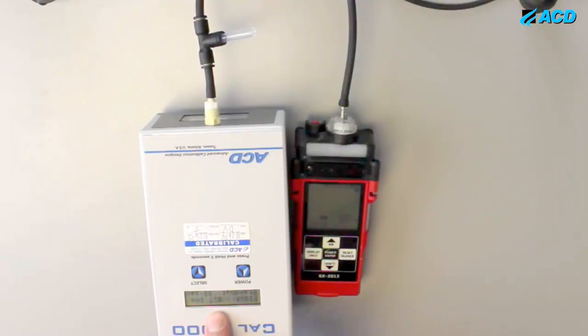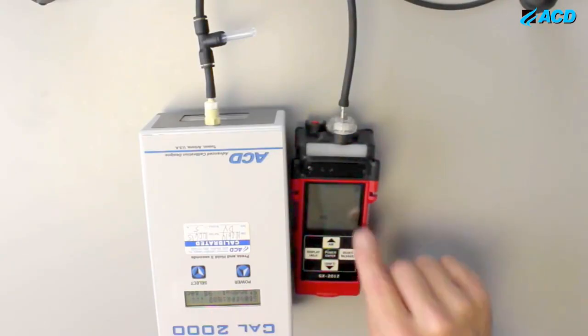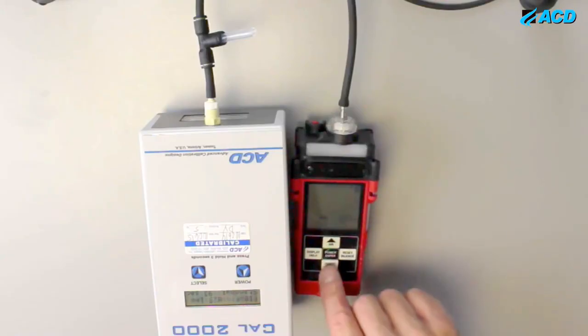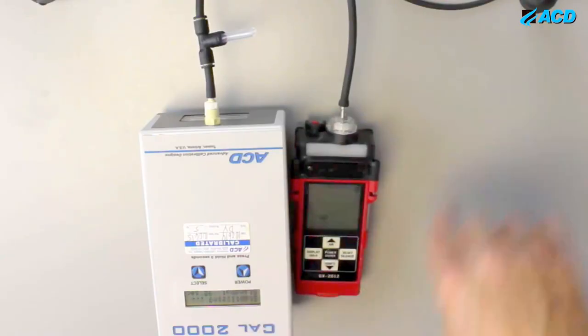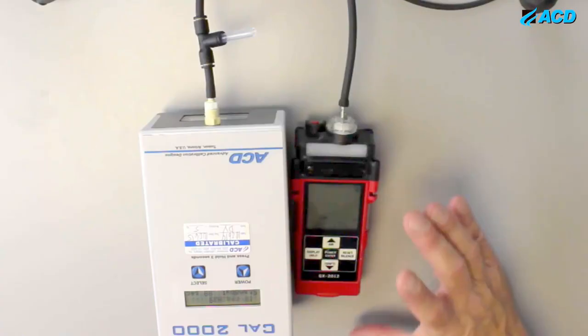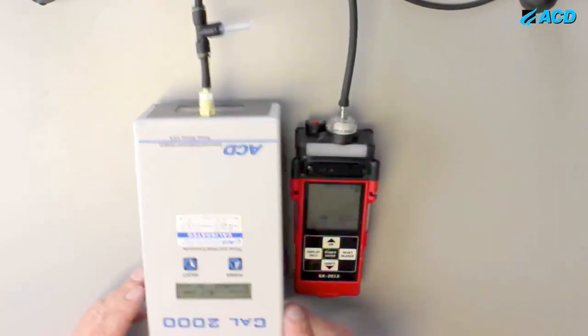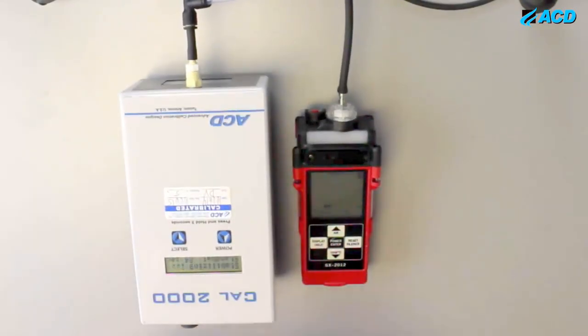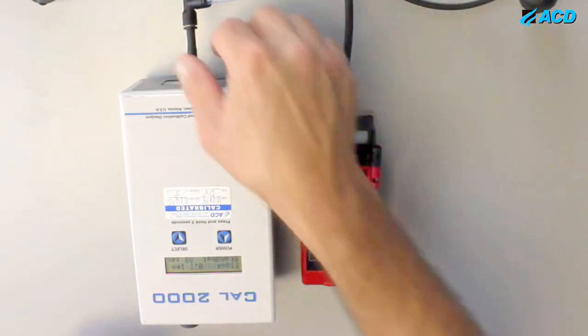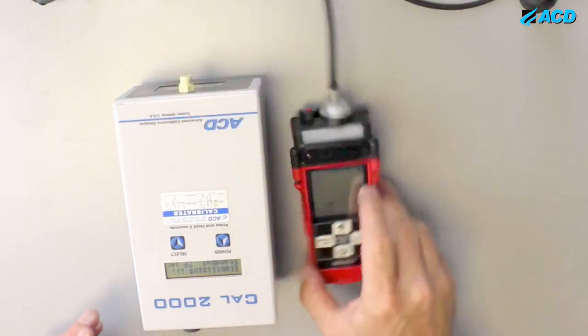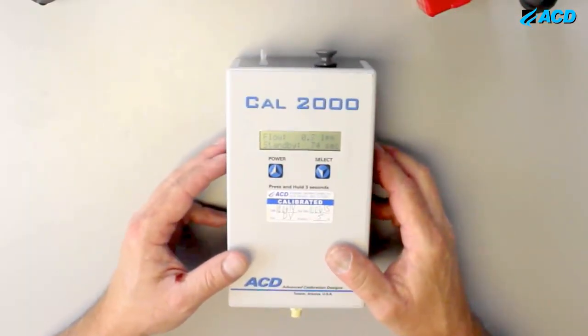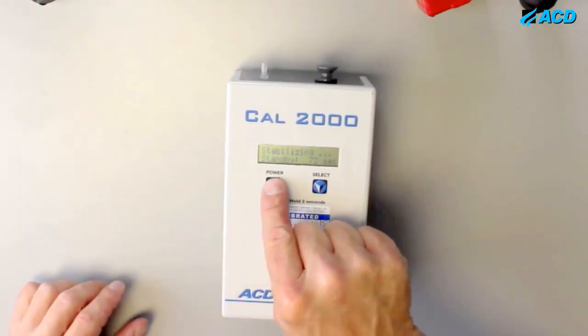Again, you would wait until this is stabilized. It's counting down to like 100 seconds here. And then you'd go into the calibration routine, set it to 10 parts per million, and go to the next and the next. And the advantage of using that mode is that you don't have to wait for a stabilization period between instruments. Okay, so when I'm all done calibrating everything, and I unhook that and I'm done for the day, the way to power off the unit is to press and hold the power button for 3 seconds again.